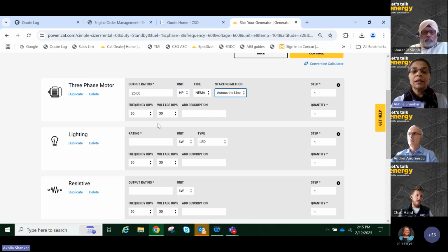sizing exercise. You also can define the frequency dip limit and the voltage dip limits that are acceptable. Ideally, and for the most optimum sizing of the generator set, we recommend that you leave it at the recommendation that is shown. These are the frequency and voltage dips that can be tolerated by that specific load. So I will leave it at 30% for this exercise.